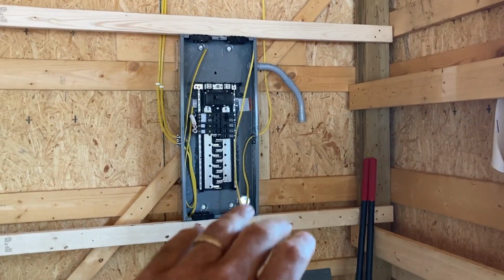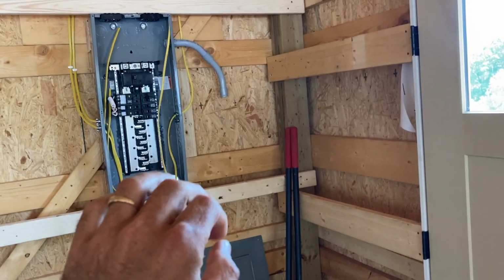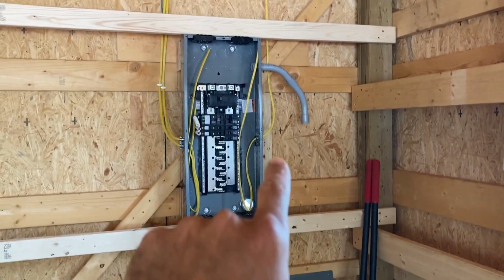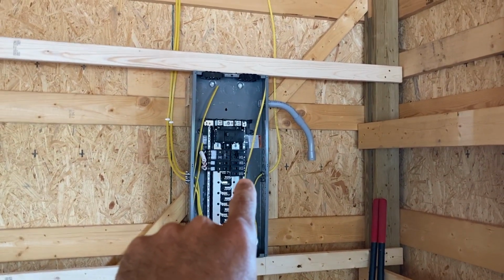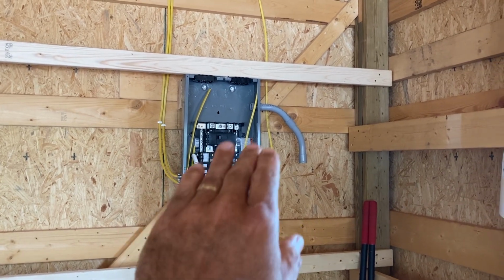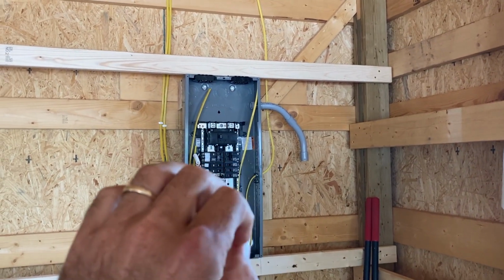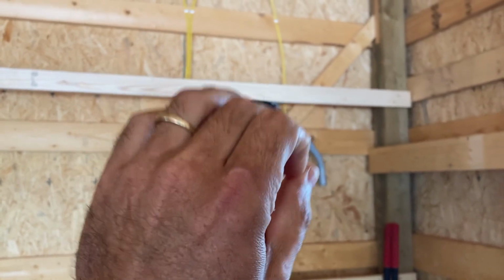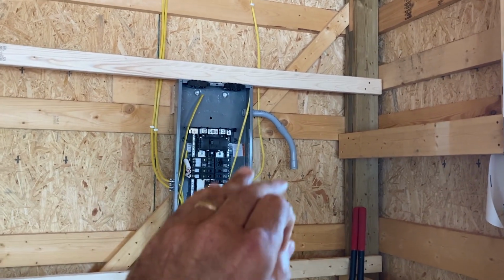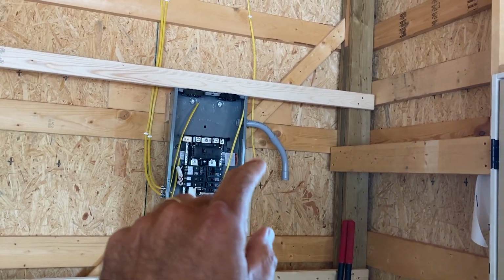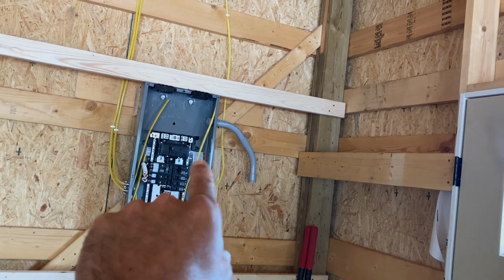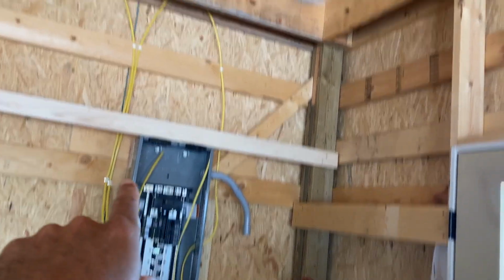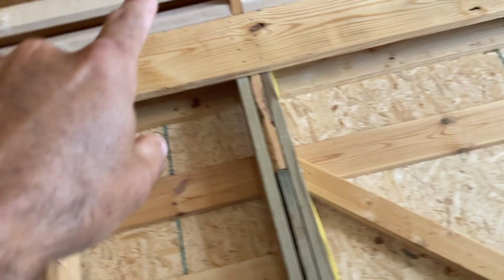All right, I'll show you how I did this first plug as an example. I came from my breaker panel, using 12-2 wire because all my receptacles are going to be 20 amp receptacles, and I wanted a 20 amp circuit. So for 20 amps, you use 12-2 wire, and I ran my wire out of the panel, up and over and down my post.